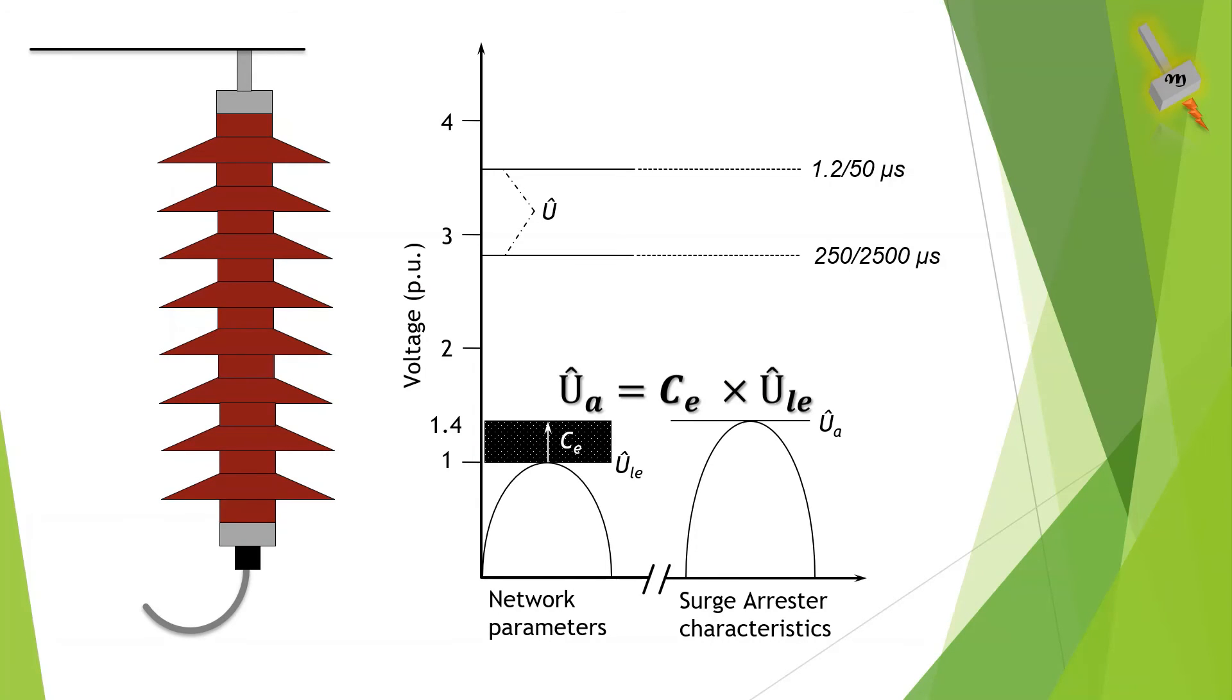Usually the earth fault factor is assumed to be 1.4 but system designers determine this based on the positive negative and zero sequence impedance of the system. To learn more on the earth fault factor we can take it in a different video.